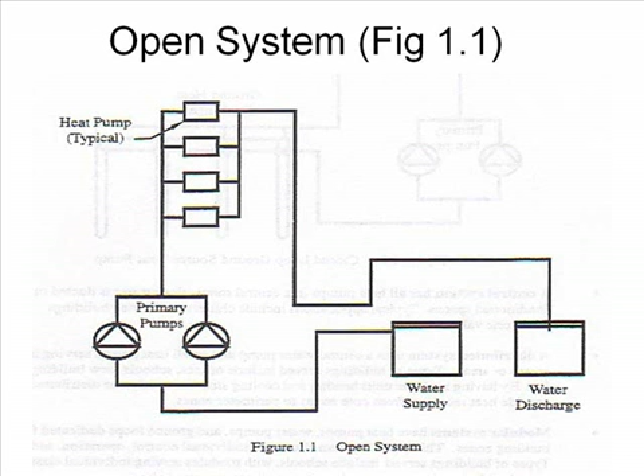Ponds are good. The heat exchanger in this pond can be a closed loop. It could be an open loop where you're pumping water through a plate frame heat exchanger inside the building and then extracting the heat from that pond water which is being circulated through that plate frame heat exchanger. Or the pond could have a series of coils in the pond, and there have been some very large systems both ways. There's one up in Iowa, about 1,000 or so tons, a big system, and it uses coils of pipe in the pond for the heat exchanger. And the Water Furnace building up in Fort Wayne, Indiana has the same thing on its building. They have a pond out there and coils of plastic pipe in that pond. So it's a very common and a very good heat exchanger system.